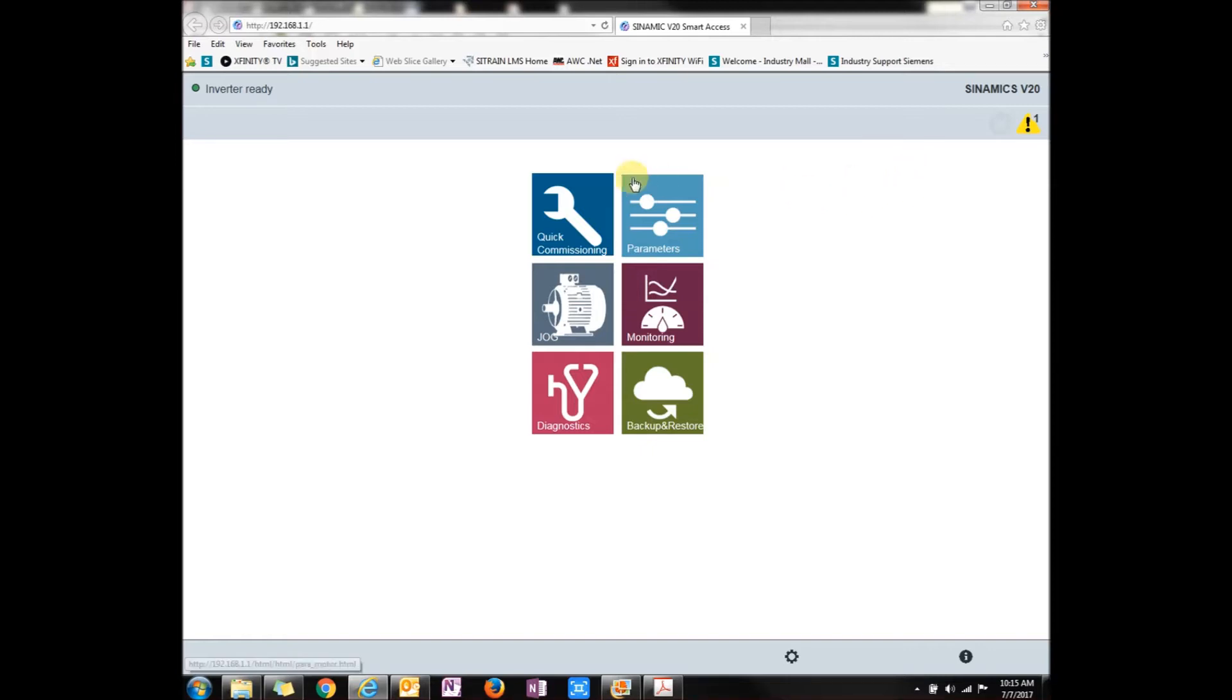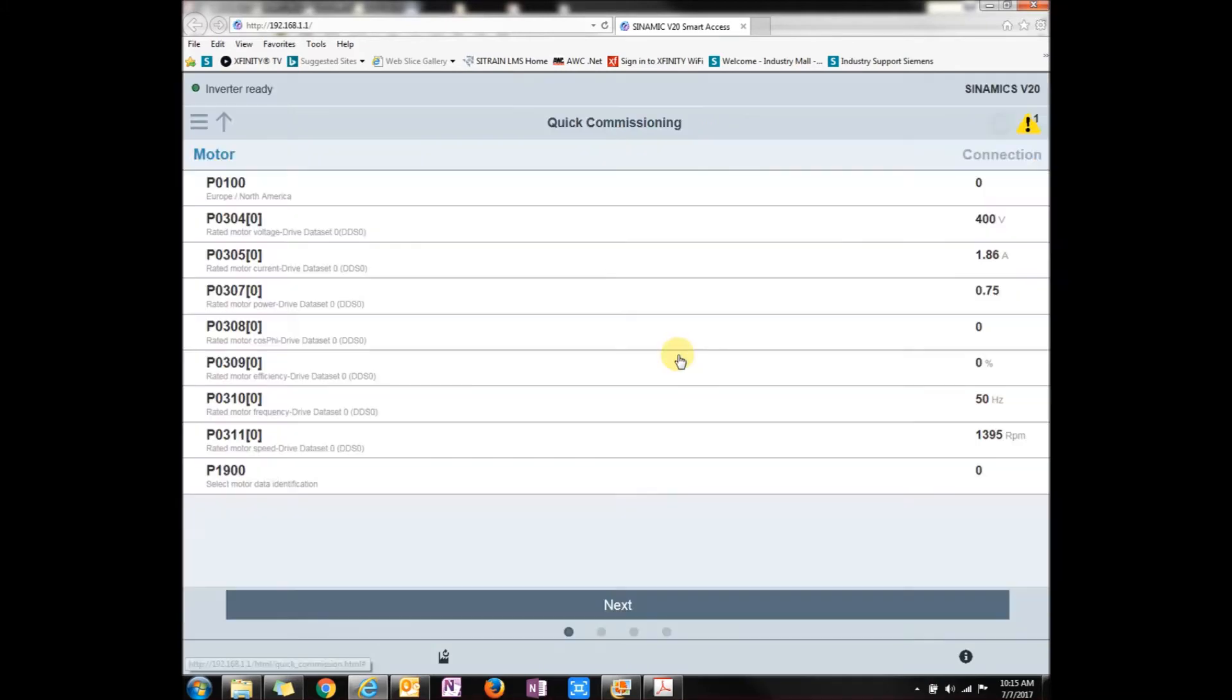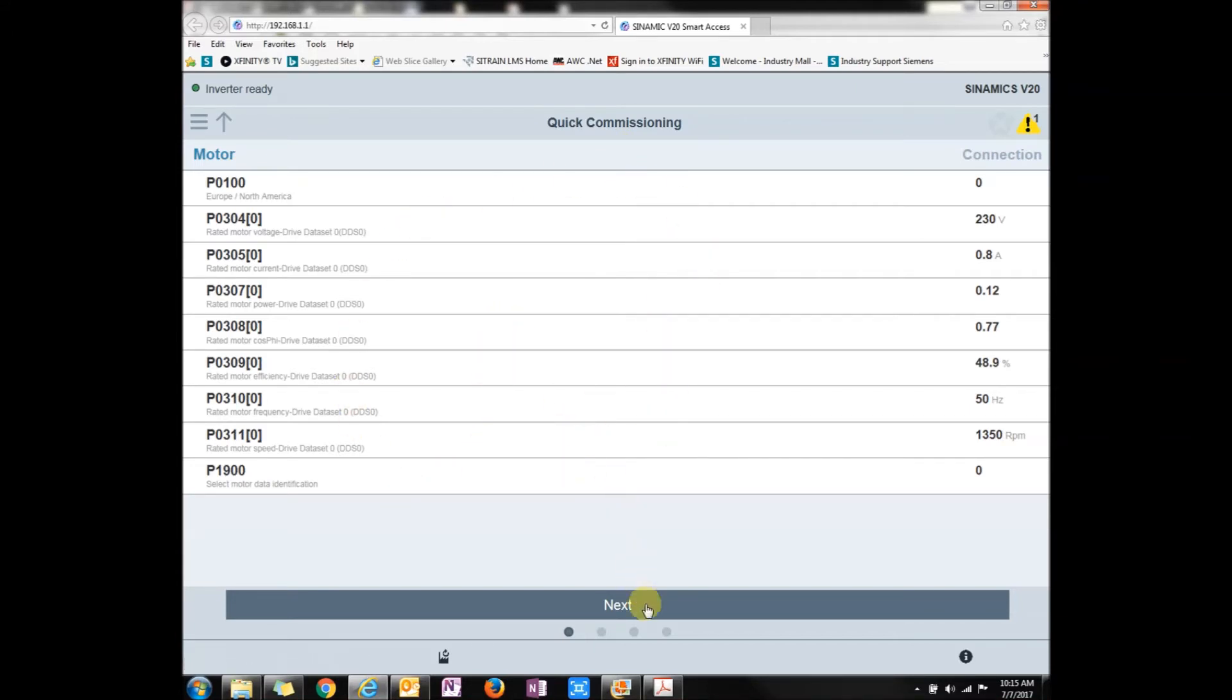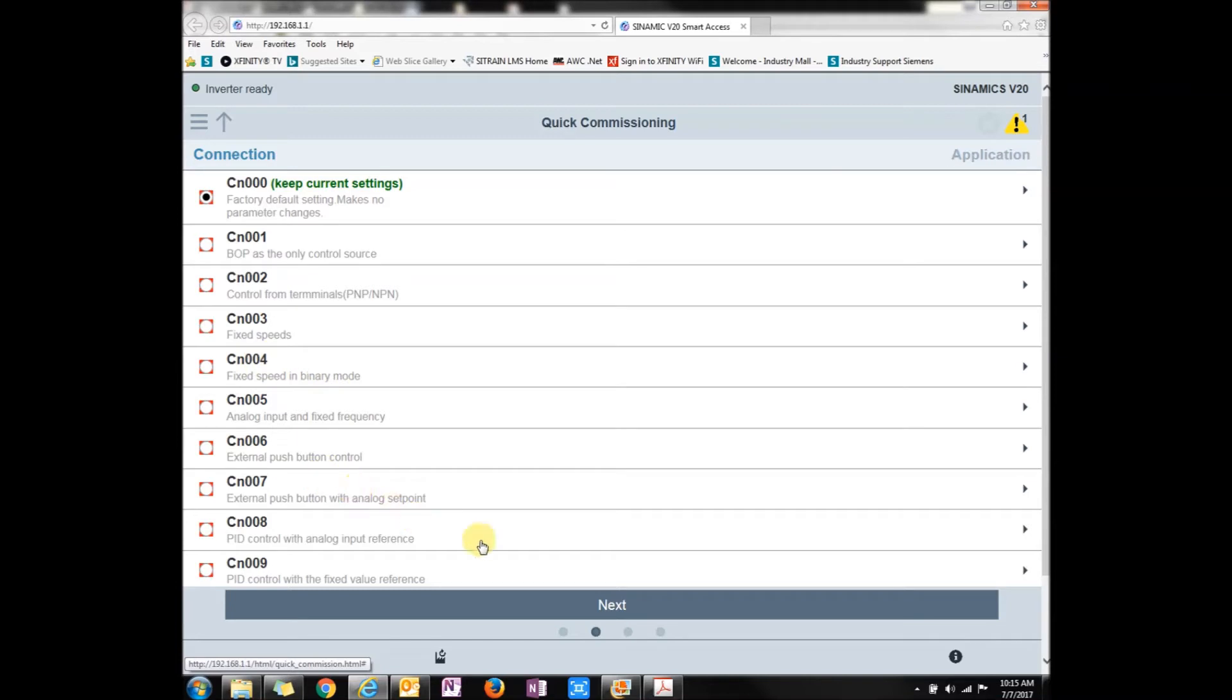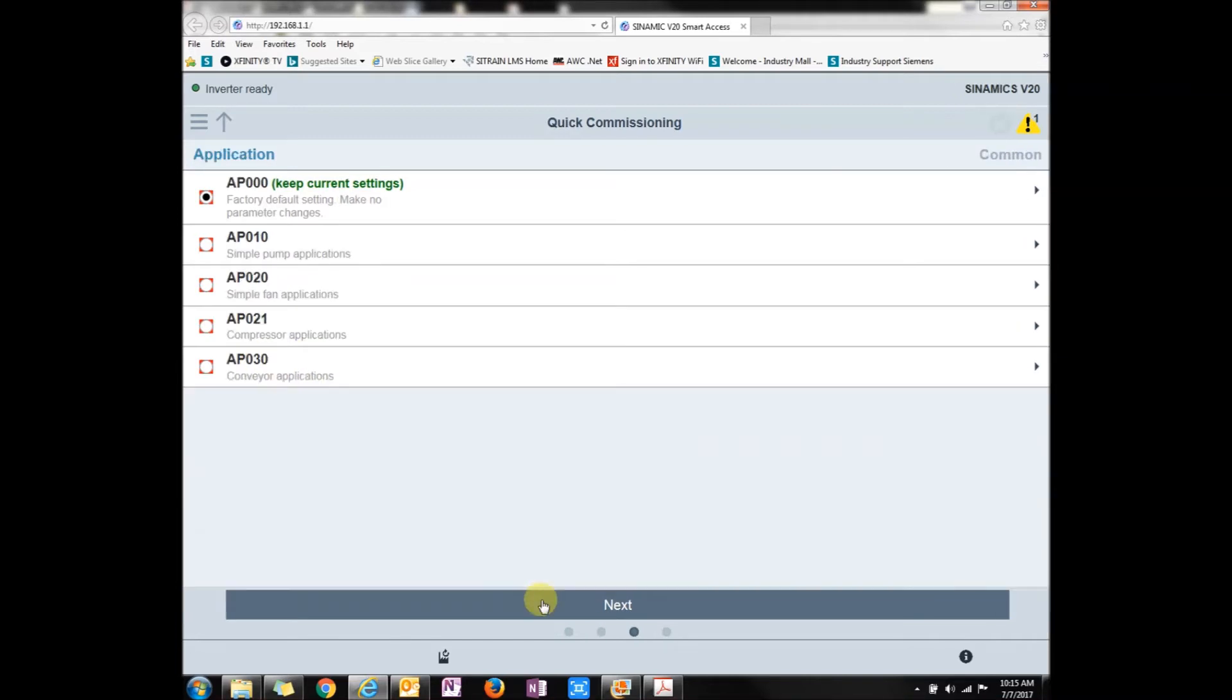Let's go to the quick commissioning and look at that. You want to start quick commissioning? Yeah. This would be your typical motor nameplate that you have to put into the drive to be able to commission it. Then you can go to how you're going to control your control macro, from BOP, fixed speed, from push buttons, whatever that might be.